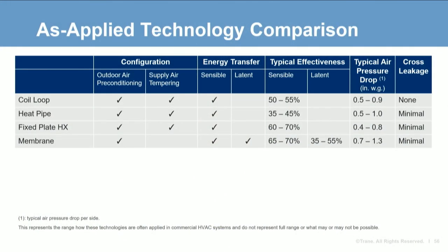Filling in the table for membrane exchangers: they have a sensible effectiveness similar to metal plate exchangers but for a little higher pressure drop, they also do latent recovery. Just remember this is as applied — membrane exchangers are typically applied at 30 to 40% lower face velocity than a metal plate exchanger.